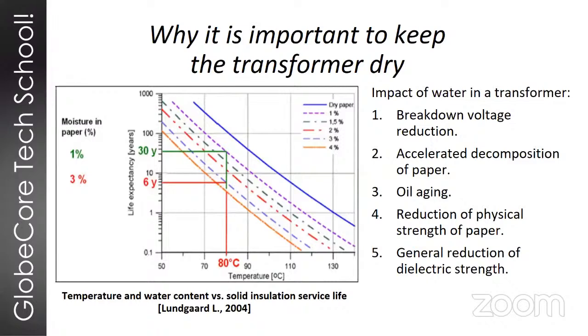An increase of moisture has quite a bit of negative effects for transformers, such as the reduction of dielectric strength of the oil, increased degradation of paper, oil aging, and a reduction of the oil's performance. And basically, all of these are bad for the transformer. Next slide, please.